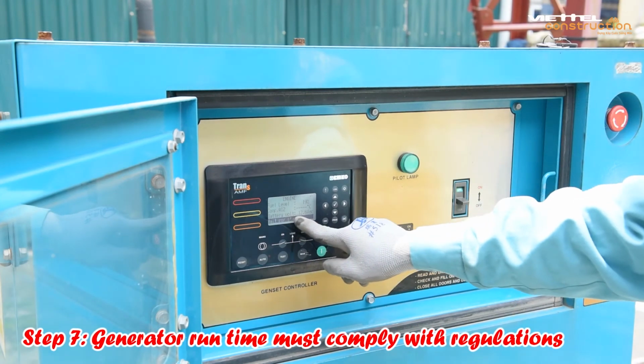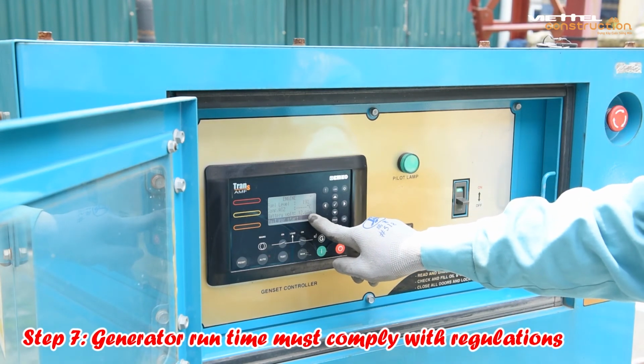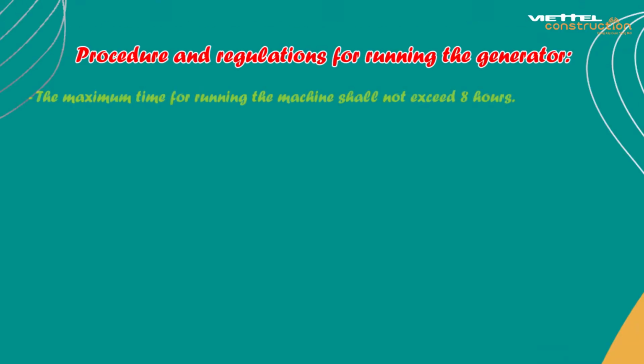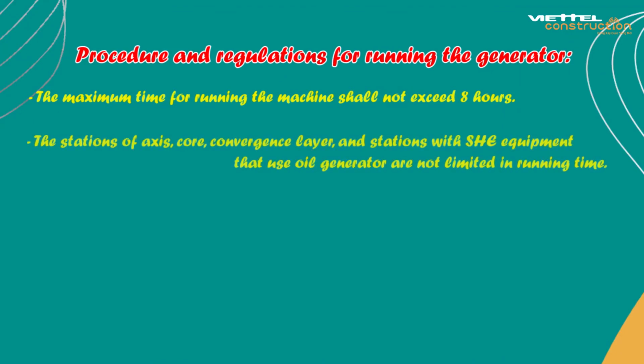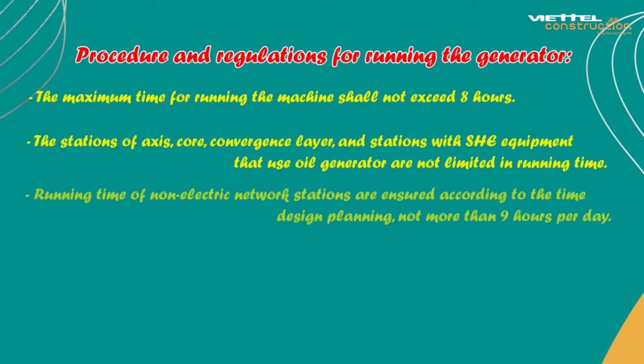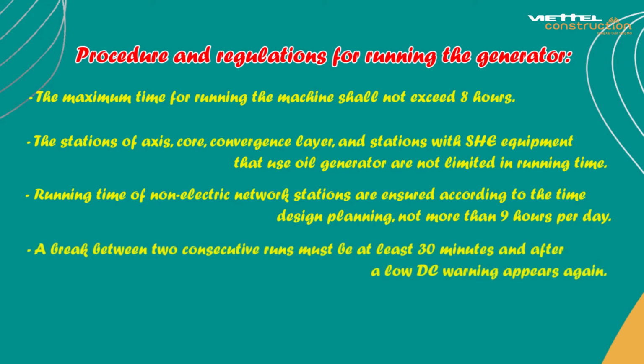Step 7. Generator run time must comply with regulations. The maximum time for running the machine shall not exceed 8 hours. The stations of axis, core, and convergence layer, and stations with SHE equipment that use an oil generator, are not limited in running time. Running time of non-electric network stations is ensured according to the time design planning, not more than 9 hours per day. A break between 2 consecutive runs must be at least 30 minutes, and after a low DC warning appears again.